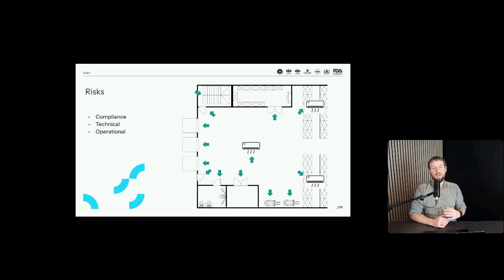So if, let's say, you plan to open 20 times a day for 10 minutes each, well, then that would be roughly once an hour or once every half an hour. And then you basically simulate this. You open the doors, 10 minutes, close them, wait half an hour, open the doors, close them, wait half an hour, and so forth. And then you see the effects of those door openings on the temperatures within your warehouse.